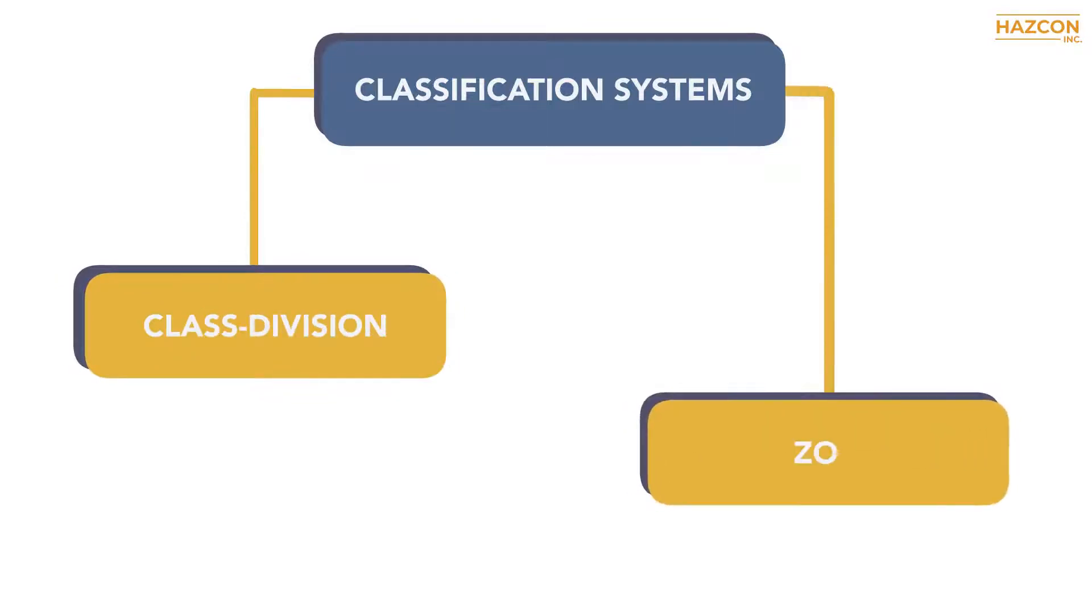Hazardous locations are classified in North America using two different classification systems: the class division and zone systems.